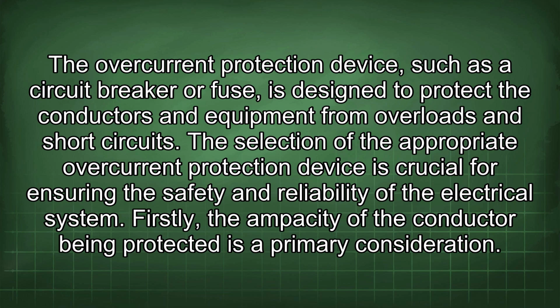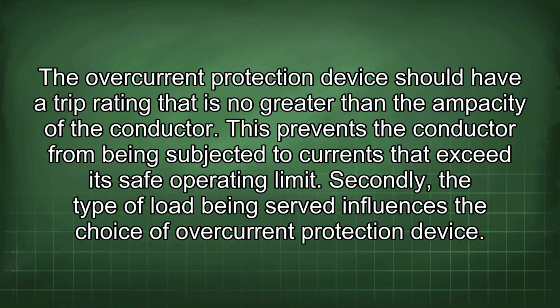The overcurrent protection device, such as a circuit breaker or fuse, is designed to protect the conductors and equipment from overloads and short circuits. The selection of the appropriate overcurrent protection device is crucial for ensuring the safety and reliability of the electrical system. Firstly, the ampacity of the conductor being protected is a primary consideration. The overcurrent protection device should have a trip rating that is no greater than the ampacity of the conductor. This prevents the conductor from being subjected to currents that exceed its safe operating limit.